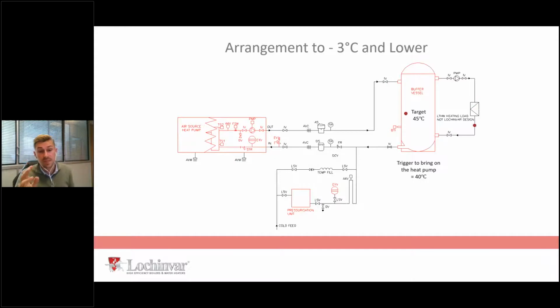Reason number two, if your system goes into defrost, you want to make sure there's energy in the system to deplete so that you can basically defrost the evaporator. If there's no energy in the system, what happens is typically you bring on an electric immersion heater, and if you do that, you've just killed your carbon savings because you're running a direct electric element. So yeah, 10 litres per kilowatt of air source heat pump is what you can expect as your rule of thumb in storage.